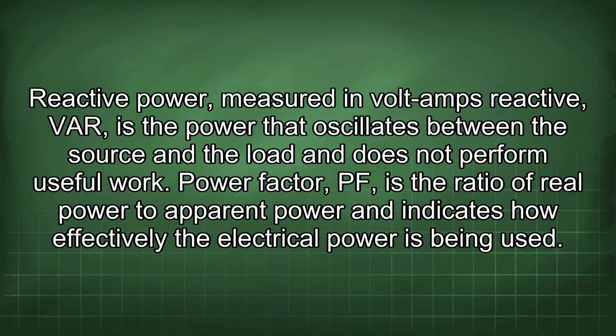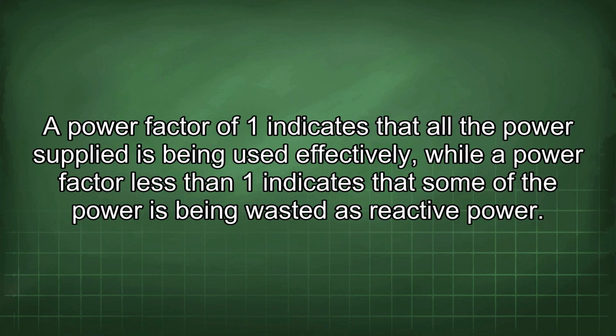not perform useful work. Power factor (PF) is the ratio of real power to apparent power and indicates how effectively the electrical power is being used. A power factor of 1 indicates that all the power supplied is being used effectively, while a power factor less than 1 indicates that some of the power is being wasted as reactive power.